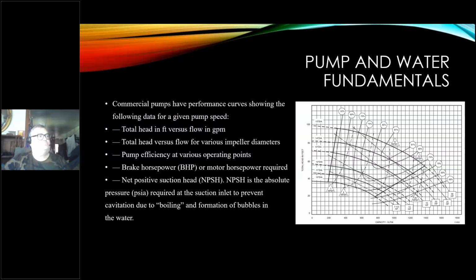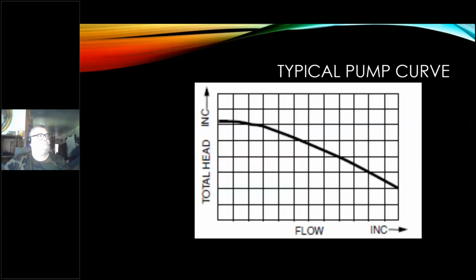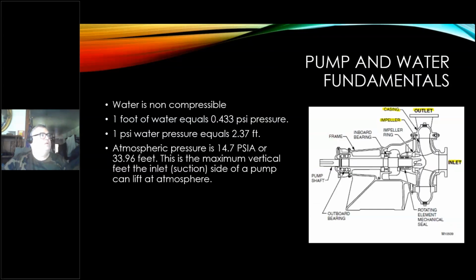Okay, and then 2 slides back, sorry. You mentioned a 33, one slide back, one more back. You mentioned a 33.96 feet. So atmospheric pressure will push water 33.96. Does that assume that the other side has a vacuum? Is that the idea, that we have atmospheric pressure on one side and a vacuum on the other? No, it's the maximum distance. Like if you were pulling out of a pit, okay, you had the suction of your pump down in a pit, a hose or something. If you've ever had to pump out a hole that's filled up with water, the hose on that pump is only 30 something feet, because you will not be able to pull the water any further than that.